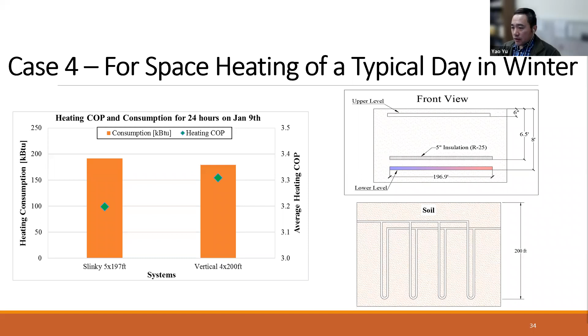This slide compares the heating performance of the heat pump when connected with dual layer horizontal slinky pipes, vertical boreholes, and an air source loop. For a given winter day, the outdoor air is too cold, around -10 Fahrenheit or below, so the air source heat pump is using the auxiliary electric heater all the time, which has a COP equal to 1. Significant savings can be achieved by using either horizontal or vertical loops compared to the air source loop.